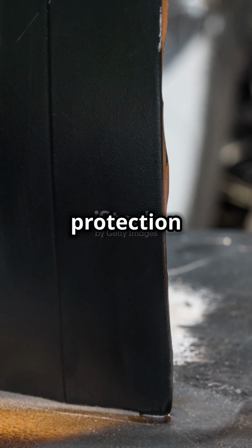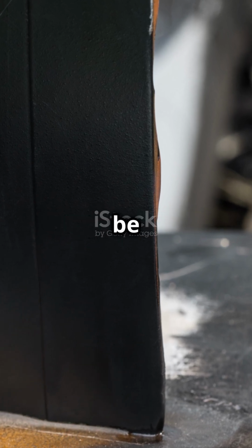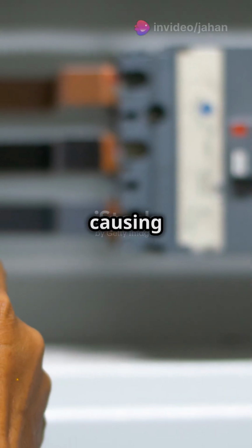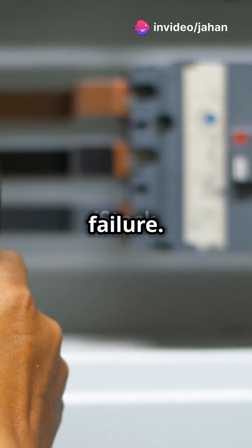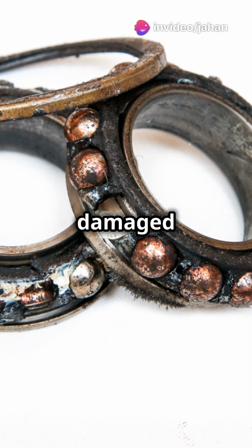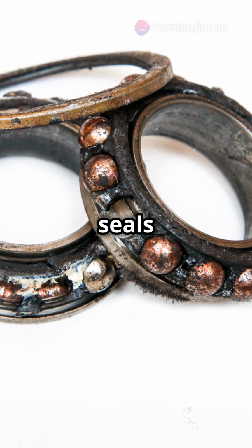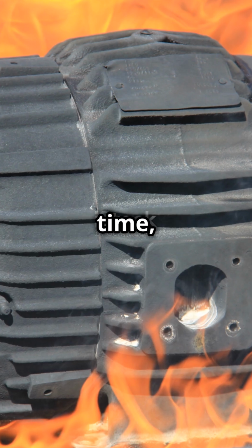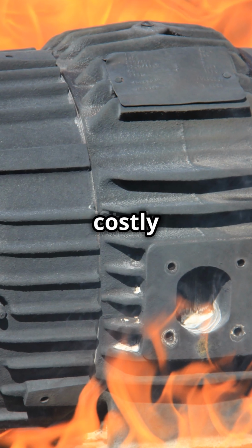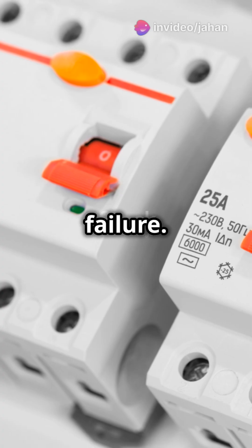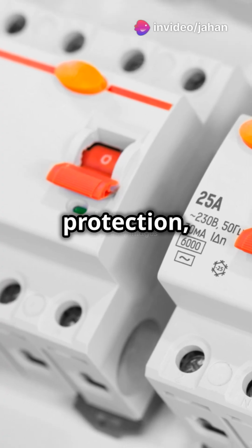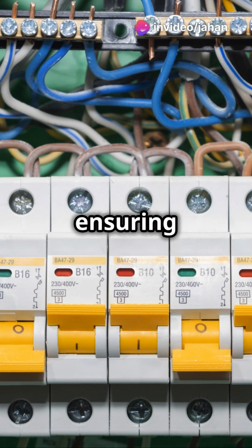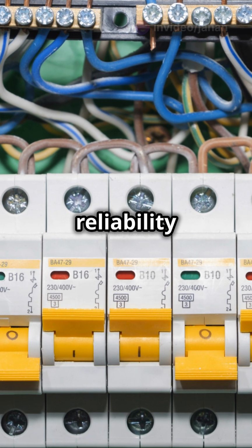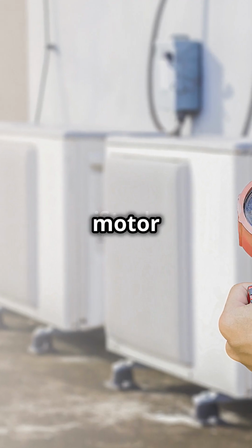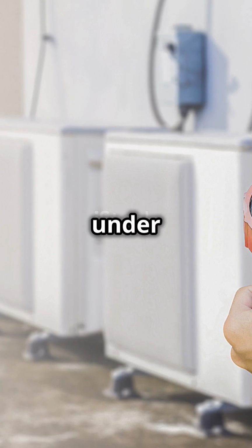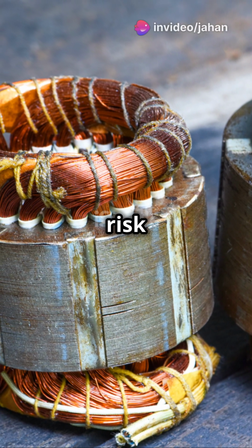If dry run protection wasn't in place, the consequences can be dire. The motor can overheat quickly, causing insulation breakdown and electrical failure. Bearings can become damaged from lack of lubrication, and seals may wear prematurely. Over time, this leads to reduced efficiency, costly repairs, or even total motor failure. Thankfully, with dry run protection, all these risks can be avoided, ensuring the longevity and reliability of motors.